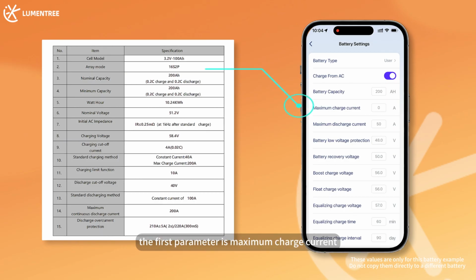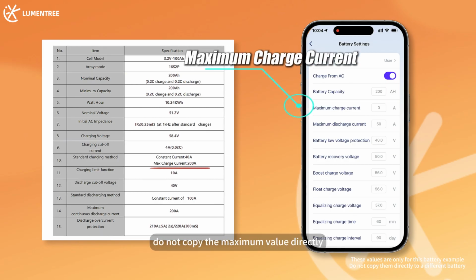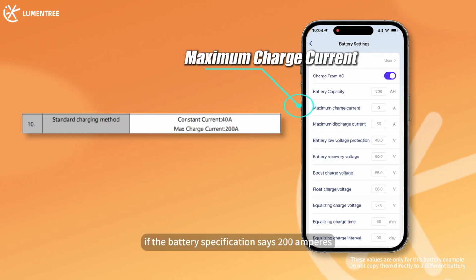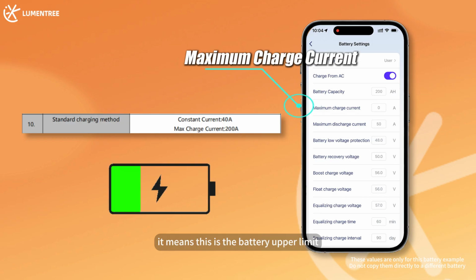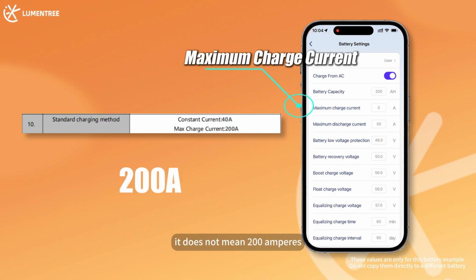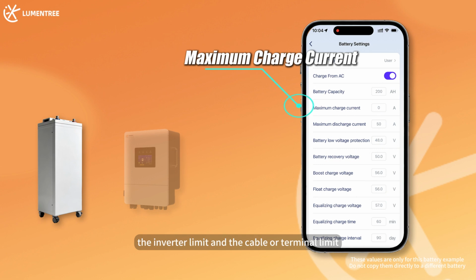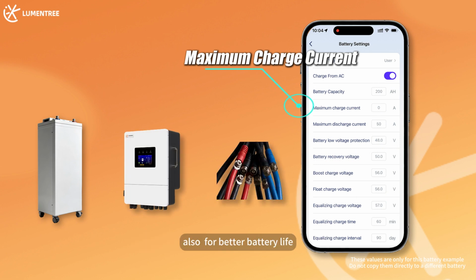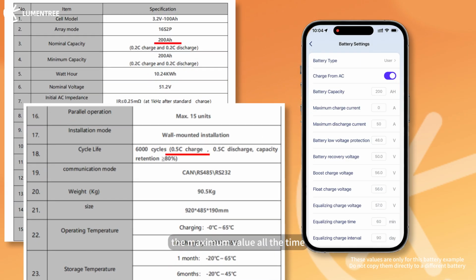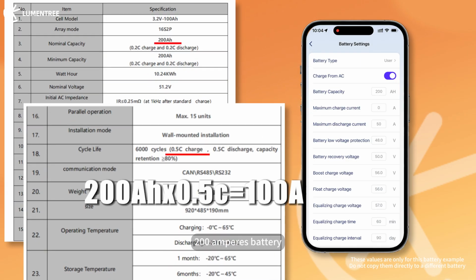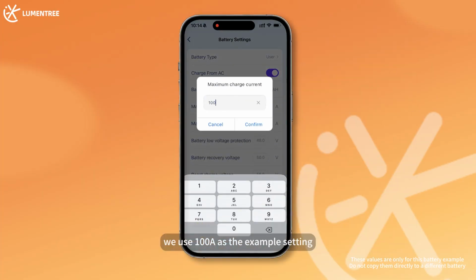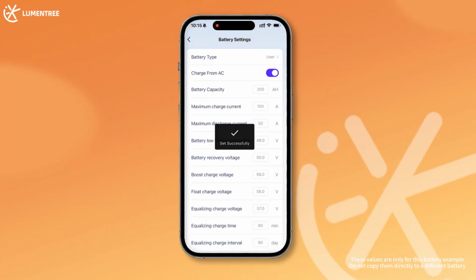The first parameter is maximum charge current. Do not copy the maximum value directly from the battery specification. If the battery specification says 200 amperes, it means this is the battery upper limit. It does not mean 200 amperes is the best setting for daily use. In real setup, this value must be lower than the battery limit, the inverter limit, and the cable or terminal limit. Also, for better battery life, it is usually better not to run at the maximum value all the time. For this 51.2 volts 200 amperes battery, we use 100 amperes as the example setting.